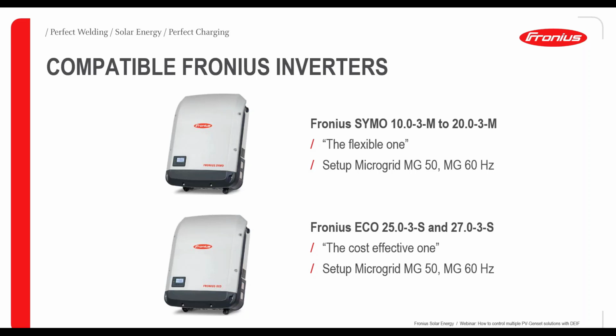So with the Symo we would have a very flexible inverter for difficult shadings, difficult rooftops to build on, for example. And with the Eco we have a very cost-effective inverter, and in combination we have a very optimum way to design a PV system. Both of them are able to set up the microgrid at 50 or 60 Hertz, depending on the region or the country we want to install in.